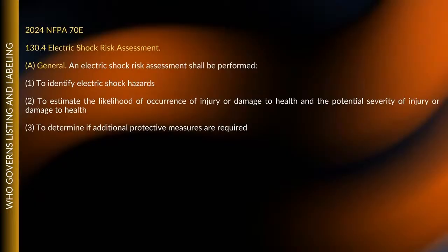Now, when you look at this, it says you have to do an electric shock risk assessment. First thing you do is identify your electrical shock hazards, then estimate the likelihood of occurrence. Let me explain this more. Likelihood of occurrence, where did I hear that earlier? Well, if you go over and look at table 130.5(C), pick up that third column, it says likelihood of occurrence.